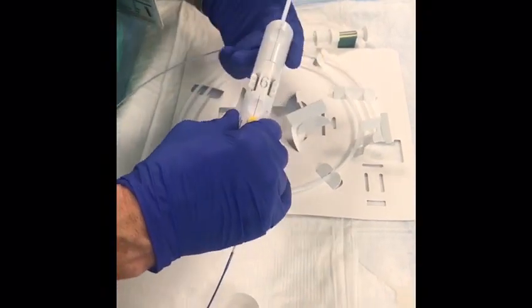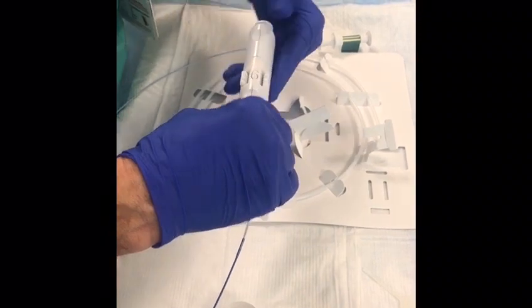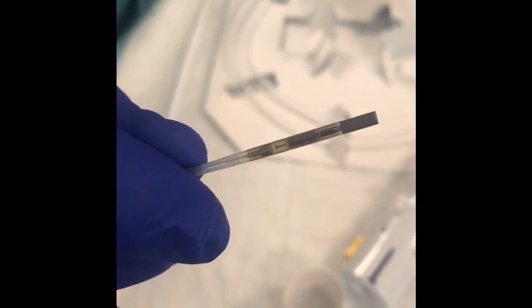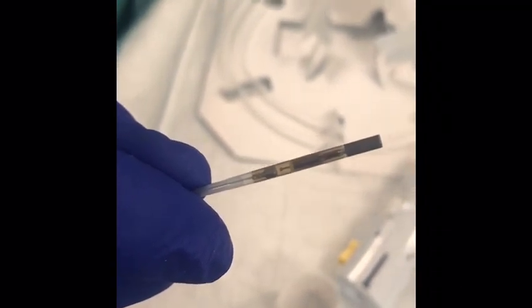Hereafter, place the valve cartridge into the loading device and then push the plunger so that the valve enters the deploying catheter. Release the deploying catheter by pressing the yellow button, and here you can see the valve is in the deploying catheter right beyond the yellow line.